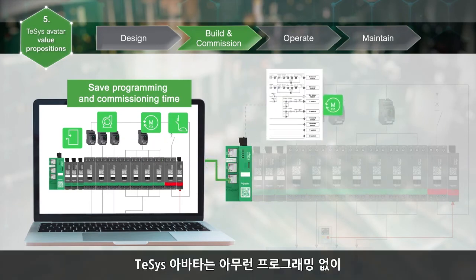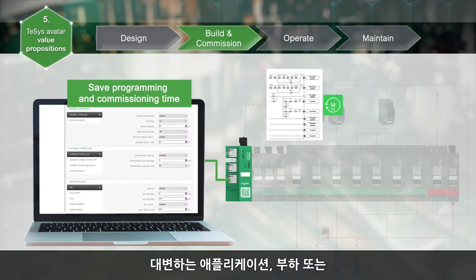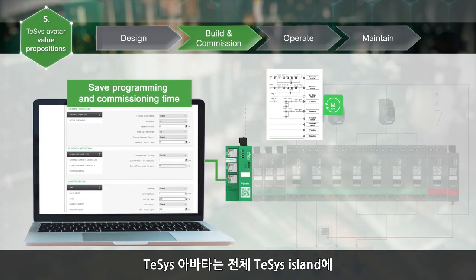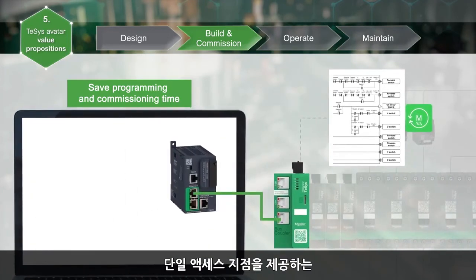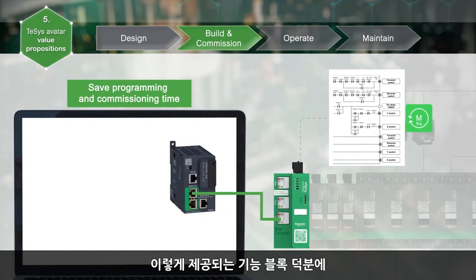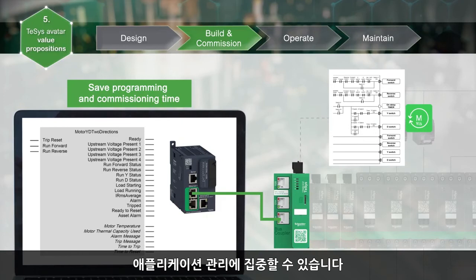TeSys Avatars embed the logic of functions without requiring any programming. Parameters are set according to the represented application, load, or device. TeSys Avatars are managed by the bus coupler, which provides only one access point for the complete island. The automation engineer can focus on the management of the load or application, thanks to the available function blocks.